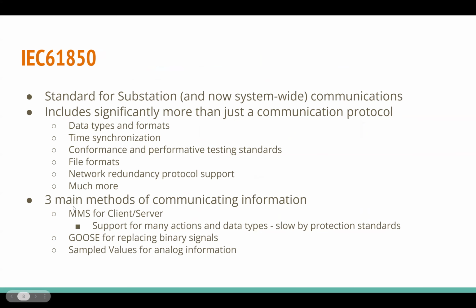The method of how we're actually doing that is 61850. You've probably heard that term thrown around, but nobody's ever cleanly explained what it is. 61850 is actually a standard, something even larger than a protocol, and it contains multiple protocols inside it. The 61850 standard has three different communication protocols: MMS, GOOSE, and Sampled Values.